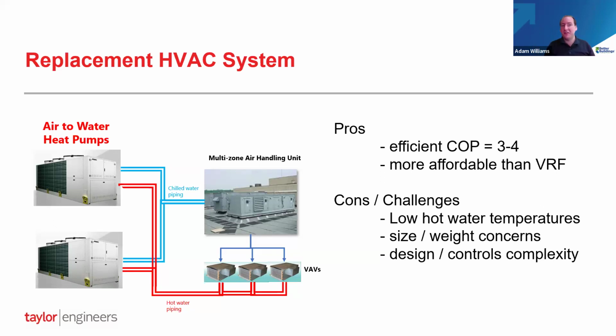And so these units can generally do both. In California, the size of units you would need to meet your heating loads is pretty close to the size you need to meet the cooling loads for general office applications. So we're going to replace our water-cooled plant and serve heating and cooling. These are a heat pump system. They are efficient, a lot more efficient than electric resistance heat. And it was more affordable than VRF because less work needed to happen down on the floor levels.